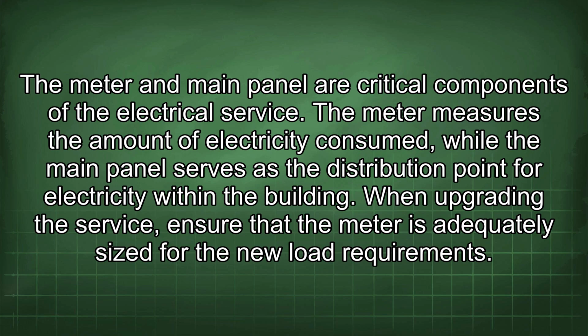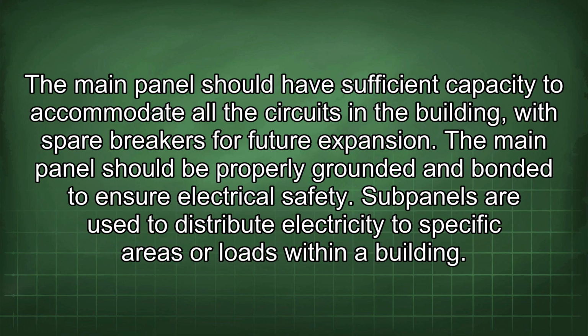The meter and main panel are critical components of the electrical service. The meter measures the amount of electricity consumed, while the main panel serves as the distribution point for electricity within the building. When upgrading the service, ensure that the meter is adequately sized for the new load requirements. The main panel should have sufficient capacity to accommodate all the circuits in the building, with spare breakers for future expansion. The main panel should be properly grounded and bonded to ensure electrical safety.